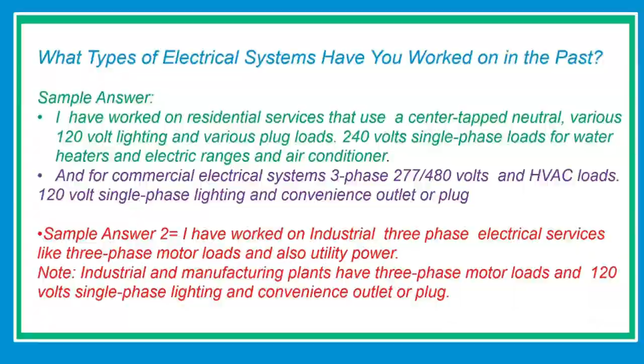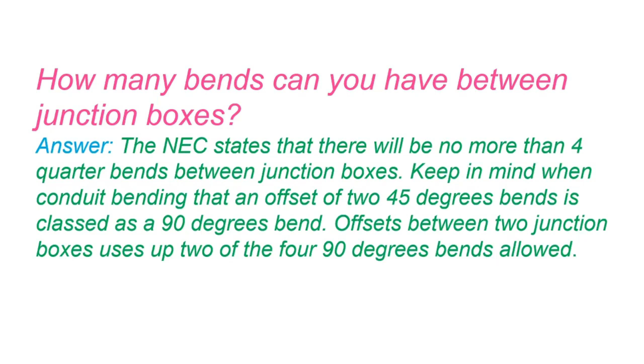How many bends can you have between junction boxes? Answer: the NEC, or National Electrical Code, states that there will be no more than four 90 degree bends between junction boxes. Keep in mind, when conduit bending, an offset of two 45 degree bends is classed as a 90 degree bend. Offset between 2 junction boxes uses up two of the four 90 degree bends allowed.